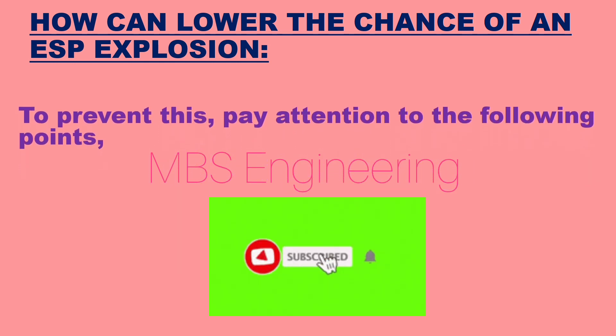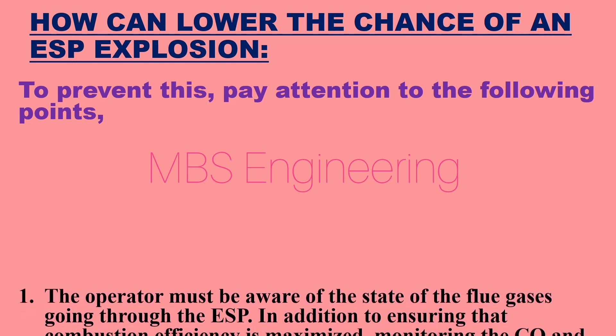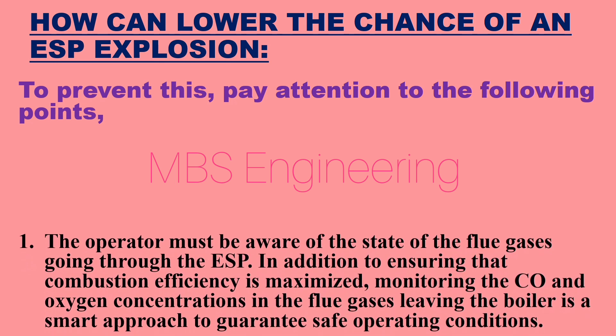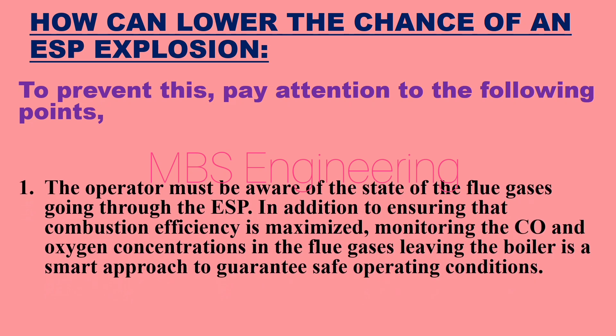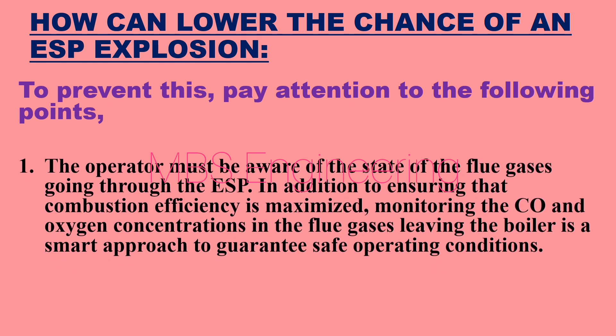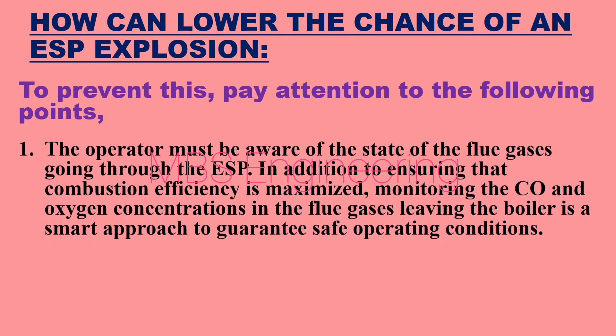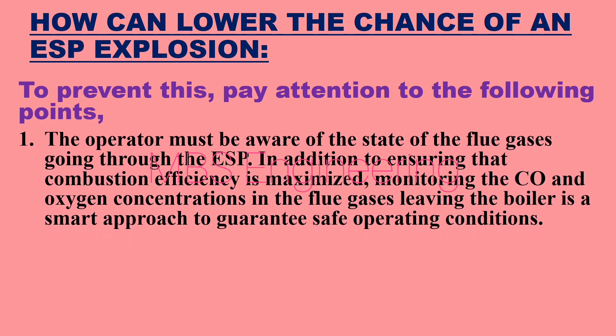Next, we will look at how to lower the chance of an ESP explosion. To prevent explosions, pay attention to the following points. Point 1: The operator must be aware of the state of the flue gases going through the ESP. In addition to ensuring combustion efficiency is maximized, monitoring the CO and oxygen concentrations in the flue gases leaving the boiler is a smart approach to guarantee safe operating conditions.